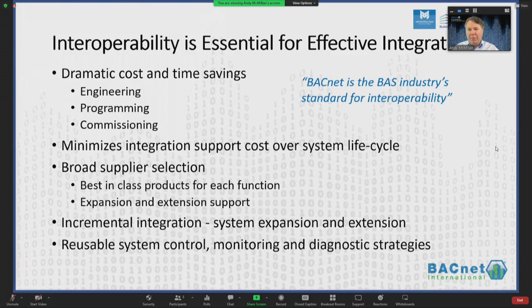To do that, we need interoperability. We need devices to just plug together so we can focus our time and energy on engineering the solution, not engineering interoperability. By starting with devices that already interoperate, we get dramatic cost and time savings, but also minimum integration support over the system lifecycle. If you build custom integrations, each time either end goes through a revision, you're probably going to be back fixing that integration. You don't have that problem with BACnet devices, because as they evolve, they stay backward compatible across suppliers.